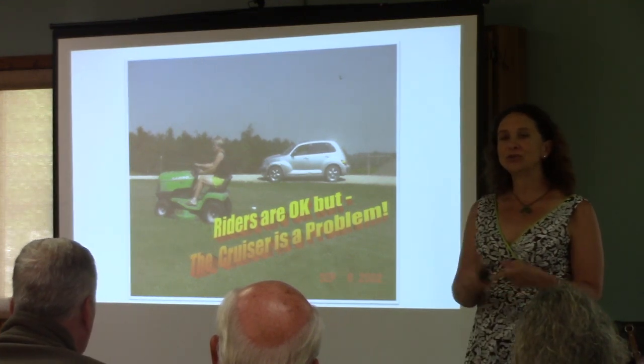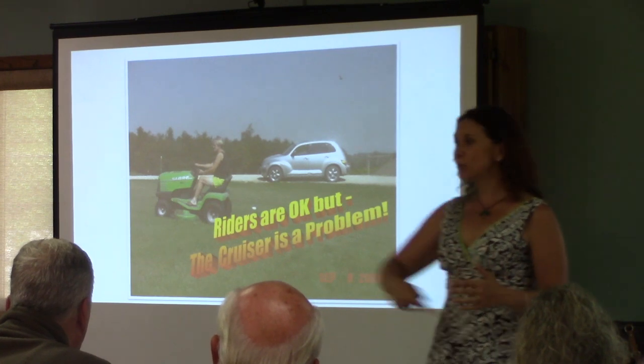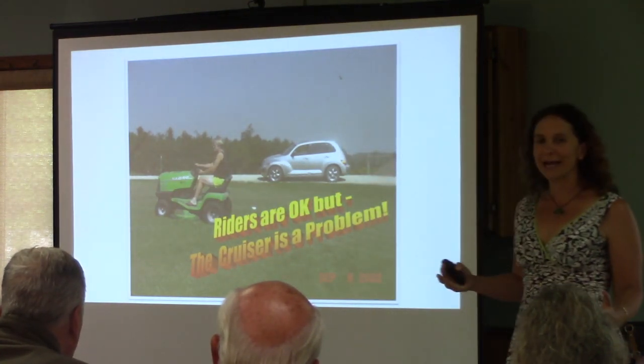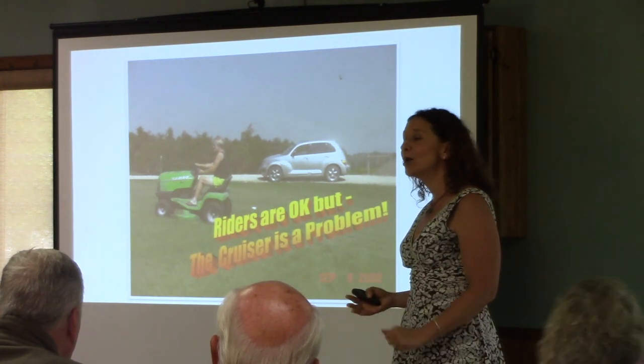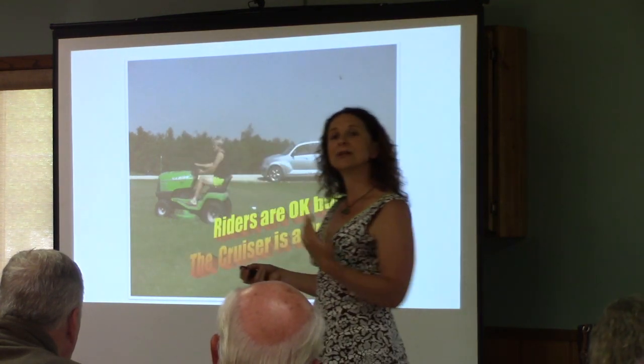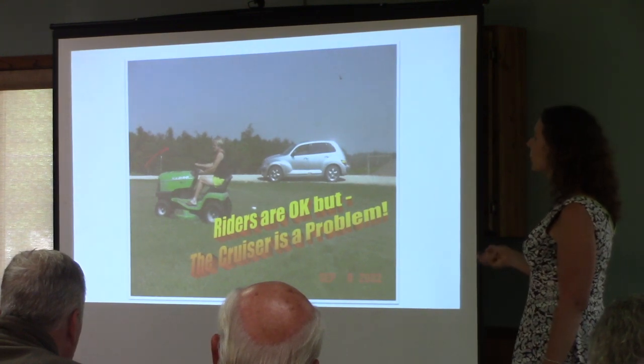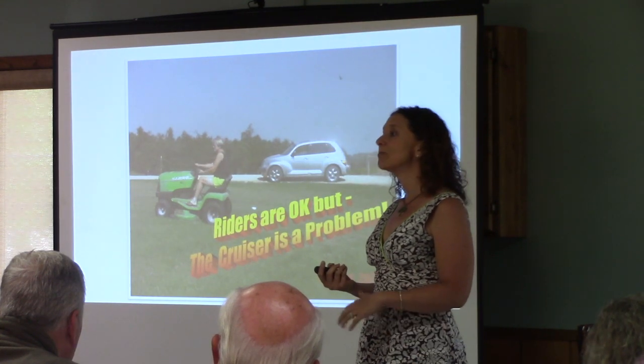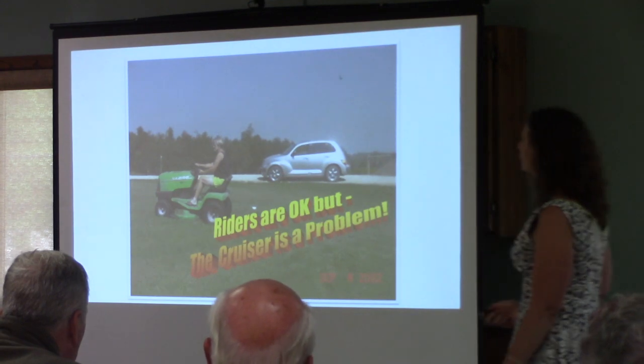When it comes to mowing, this is the biggest thing that should drive across your drain field. No trees, no tractors, no cars. Not having the wood pile on the other side. Small car, right? Not talking about big trucks or tractors, a riding lawnmower. And if you want to know how big the riding lawnmower can be, not a tractor, just a little lawnmower. And keep in mind, even with a lawnmower like this, you can compact the soil if it is wet. You don't want to be out there mowing and causing ruts over the top of your septic system.